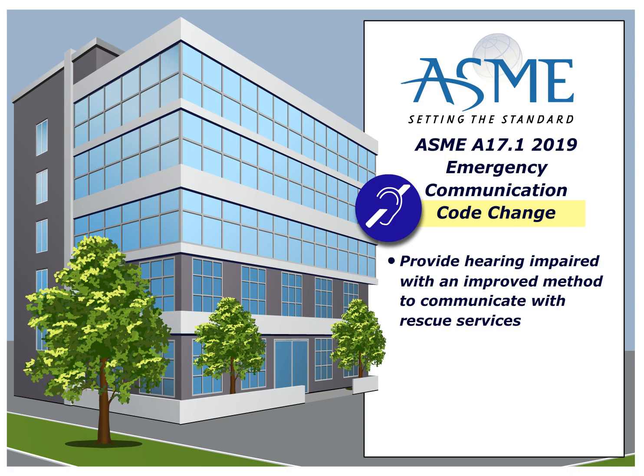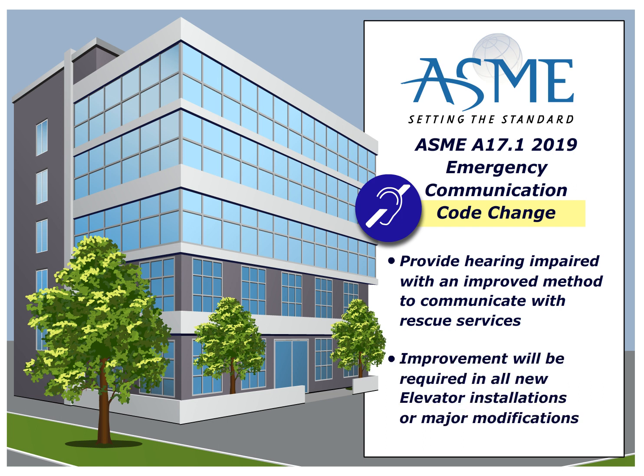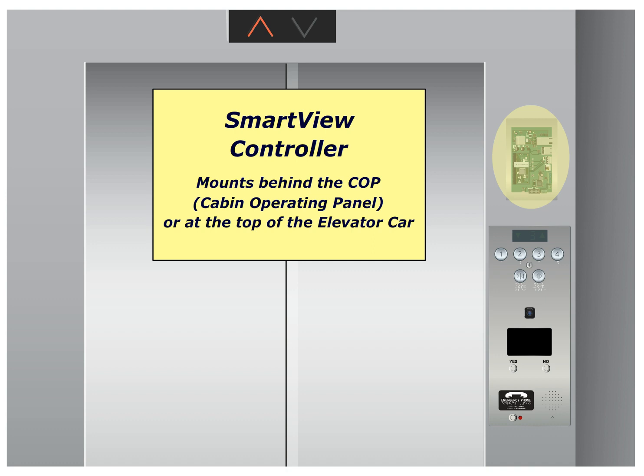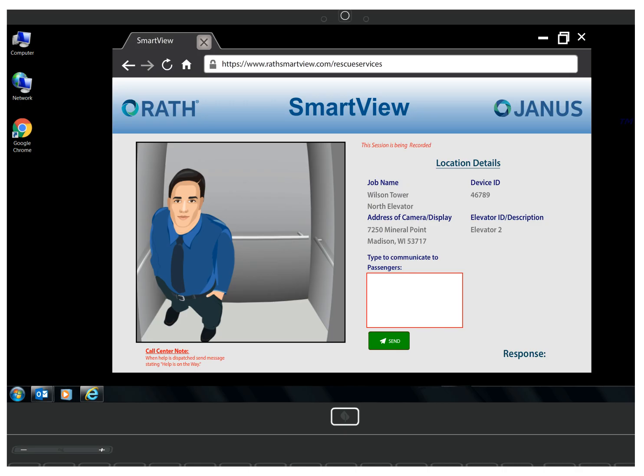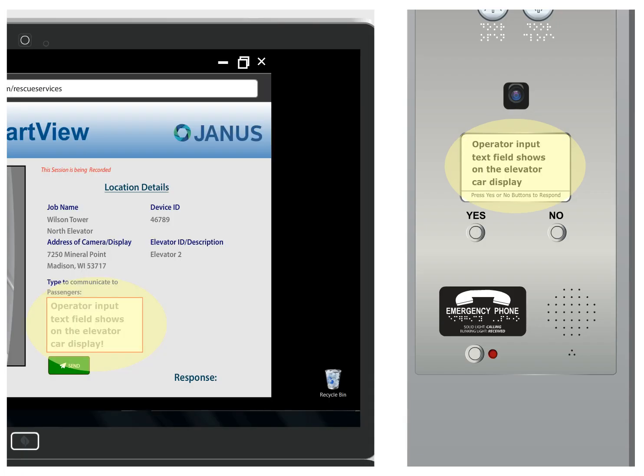The heart of the code change is to provide the hearing impaired with an improved method to communicate with rescue services. This improvement will be required in all new elevator installations or major modifications. The code requires a SmartView controller, an adjustable camera that can see the floor and be viewed remotely by rescue services, and a display on the car panel that allows rescue services to remotely ask questions by typing a message and getting yes or no responses.